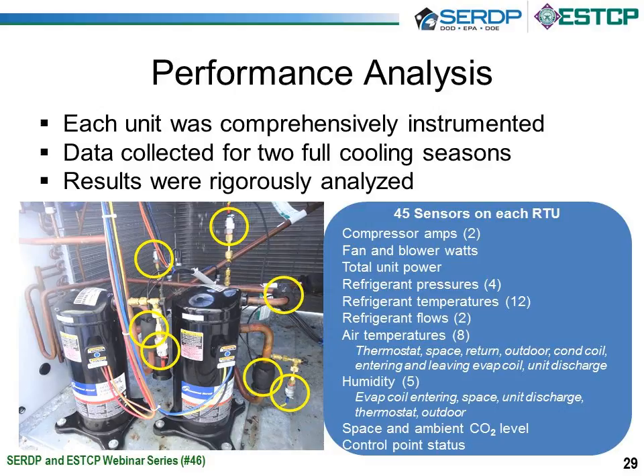The units were comprehensively instrumented. It was extremely rigorous according to ESTCP's requirements. The results, we did extensive propagation of error analysis. The end result of the energy efficiency measurements was accurate to 0.6 IEER points, or about 5% accuracy. 45 sensors on each one of the air conditioners. Pretty much the easiest way to describe that list of sensors is anything and everything was measured, all pressures and temperatures, airflows, humidities, and so forth.